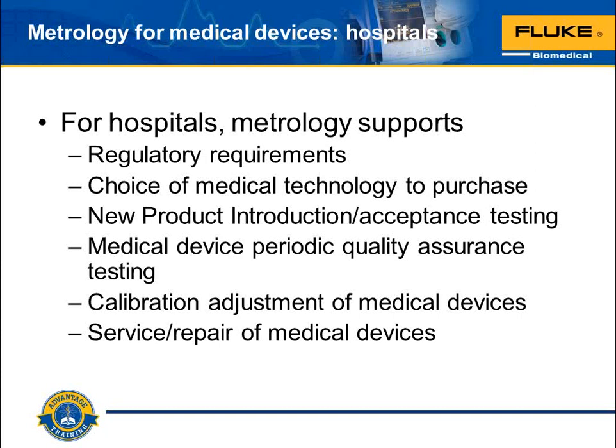New product introductions, the medical device periodic quality assurance testing, that's your PMs, and any other time that you're making measurements about that device, even in troubleshooting, the metrology matters. The calibration adjustment, that is the corrective action to bring those measurements and that calibration factor back into tolerance, and then any other service and repair for that medical device.